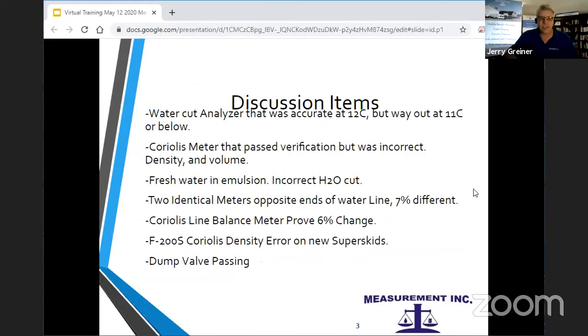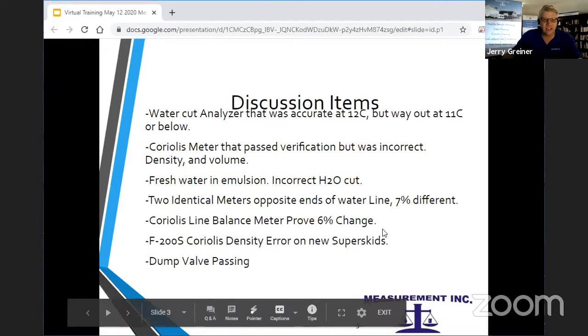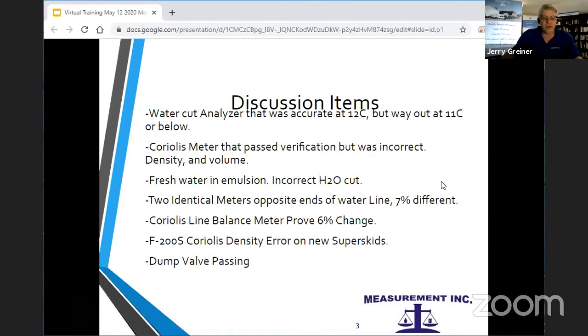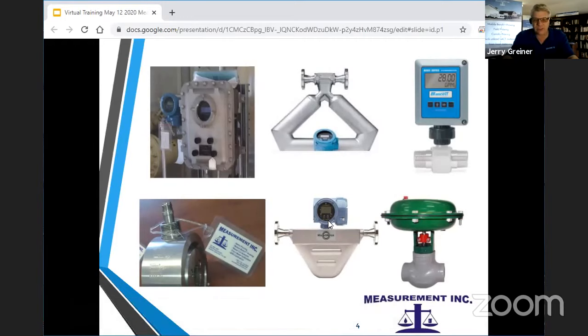Some of the items we're going to discuss today are a water cut analyzer that was accurate at 12 degrees Celsius but way out as soon as it got to 11 degrees or below. Right at that tipping point, 12 degrees or 11 degrees, is where it changed. A Coriolis meter that passed verification but was incorrect in density and volume. We're going to talk about some fresh water in an emulsion, and how that gave an incorrect water cut. Another thing is two identical meters at opposite ends of water lines that were about 7% different. We'll talk about a Coriolis meter that had a 6% change in it, and it was the Coriolis line balance meter.